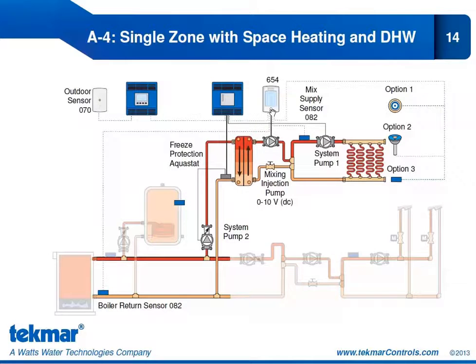So once we configure that terminal to boiler return sensor, it means we can no longer connect an outdoor sensor to the 654. However, since we are connected in the tekmarNet communication to a house control, the outdoor sensor will be connected to the house control, and that information is communicated to the 654 through tekmarNet communication.